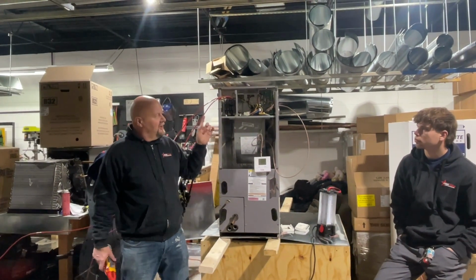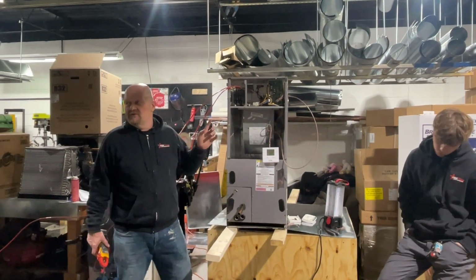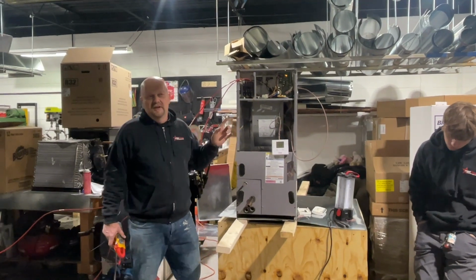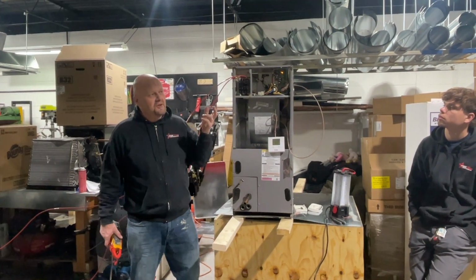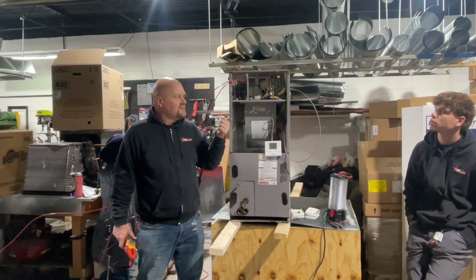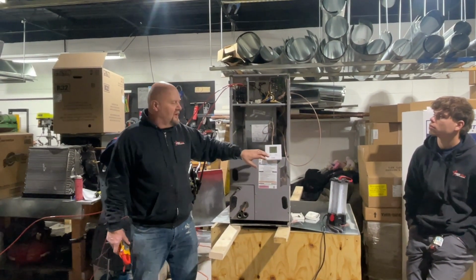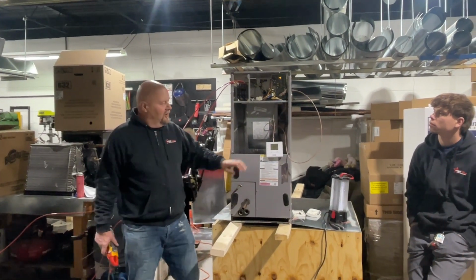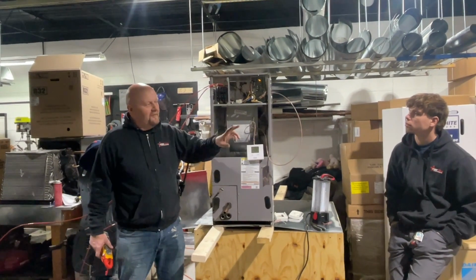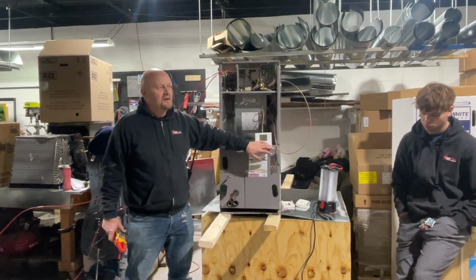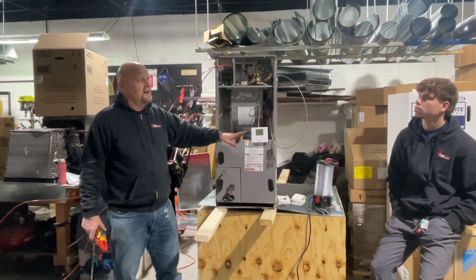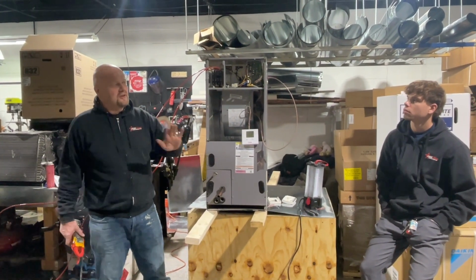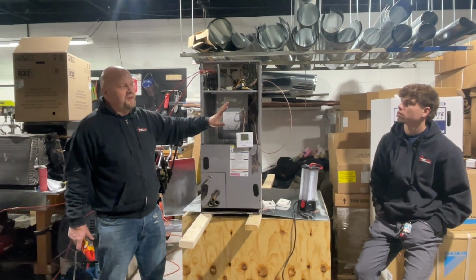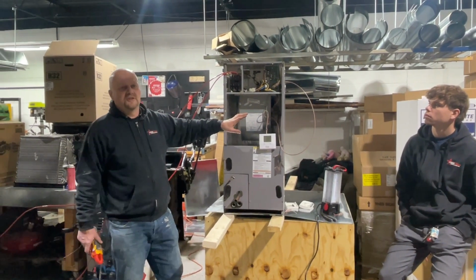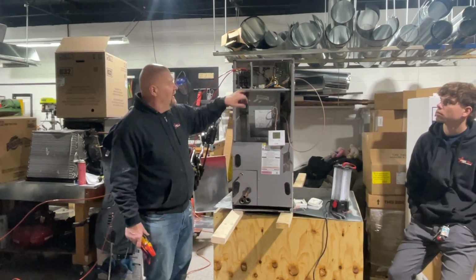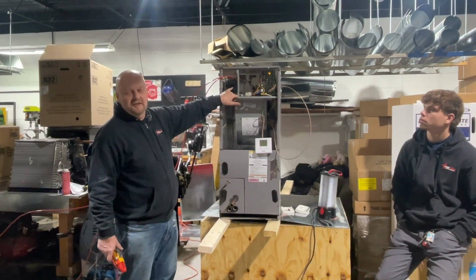That is typically what you connect to a separate or auxiliary electric strip inside of an electric furnace. It's the same thing for Unico. Unico has the same thing. It's got 3 controllers, and S3 will connect to the emergency heat. Not to get off topic, but on all those heat pump thermostats, when you turn on emergency heat, it really means you're running on that other than everything else in your heat pump or other source of heat. It literally knows that it's in emergency, so everything else is broken down. It could be used for that, or it could be used as a second stage, as W2.